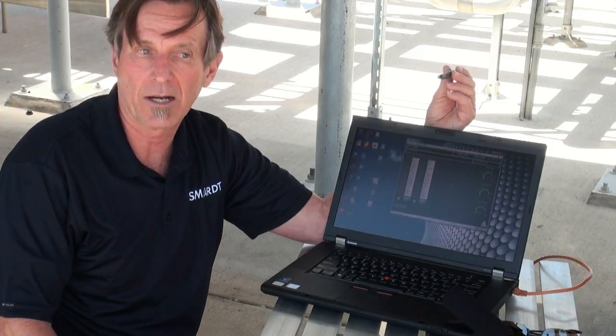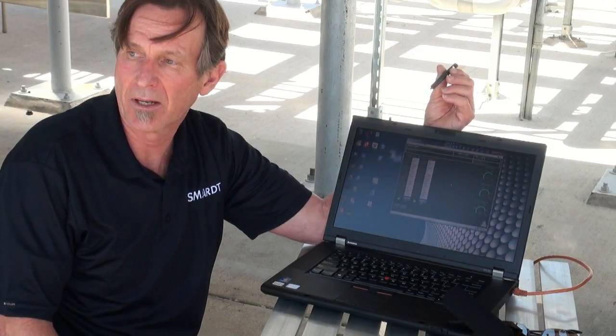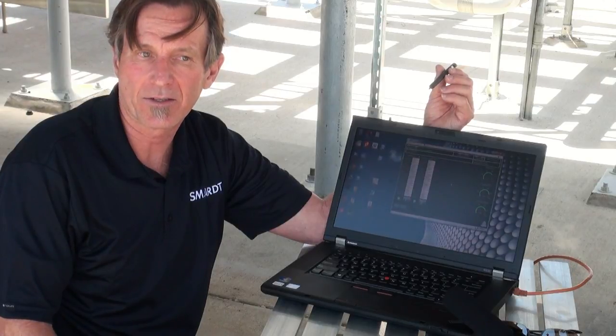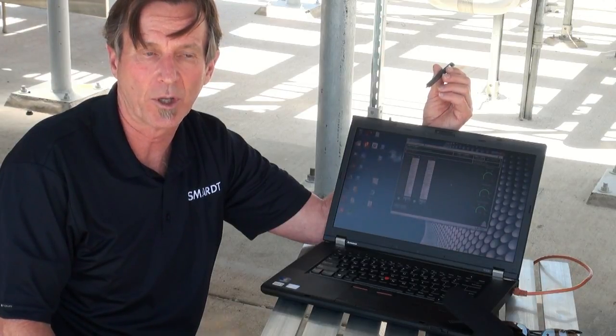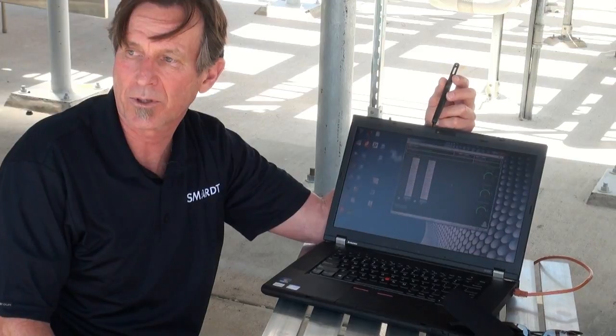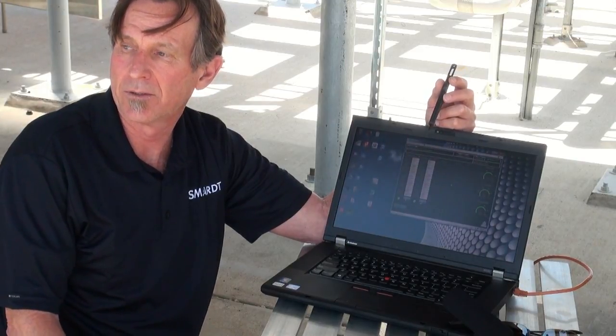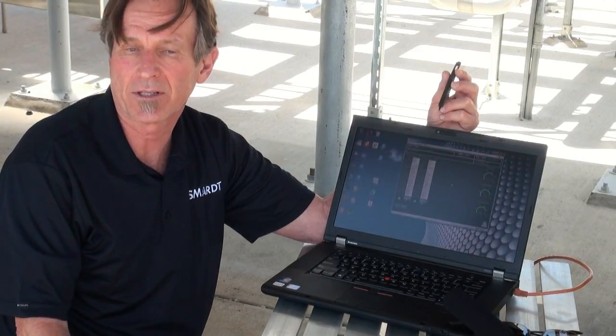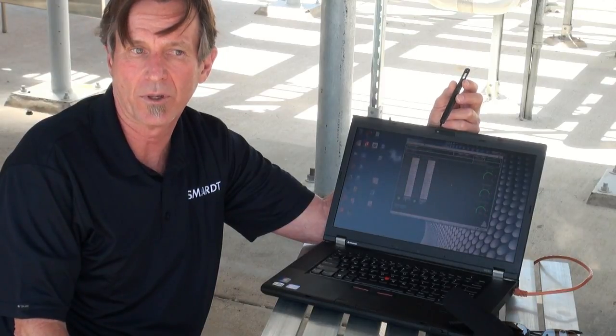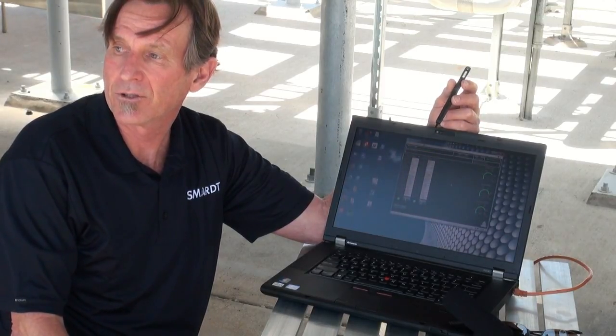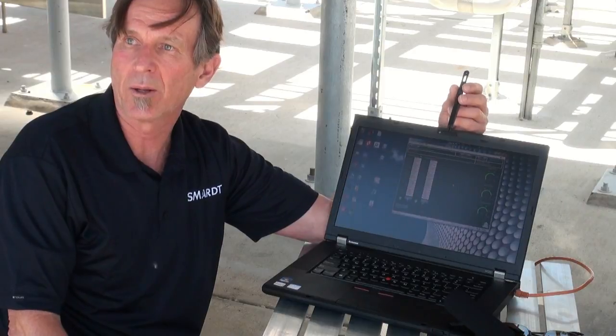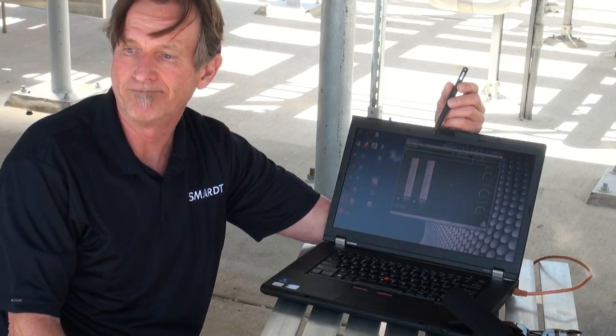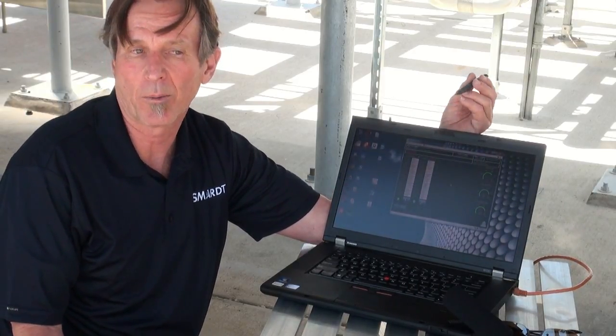Choke speed is maximum speed, and it's the point where you could apply more power to the compressor, but you're not going to pump any more refrigerant, so you're wasting energy at that point. So there's no point in applying more power. That's your maximum speed. You're not going to do any more work over that speed.